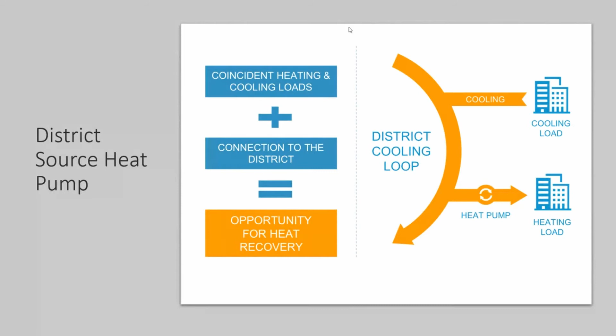The water from the heat exchanger is, let's say, 4 degrees cold, and goes to the building, warms up, and comes back at, let's say, 10 degrees Celsius. That means there's some heat energy in there. So there are ideas where we can use a heat pump on that 10-degree water and take advantage of that waste heat. Of course, temperature fluctuates over the year, and we'd have to account for that, but that's generally the idea.